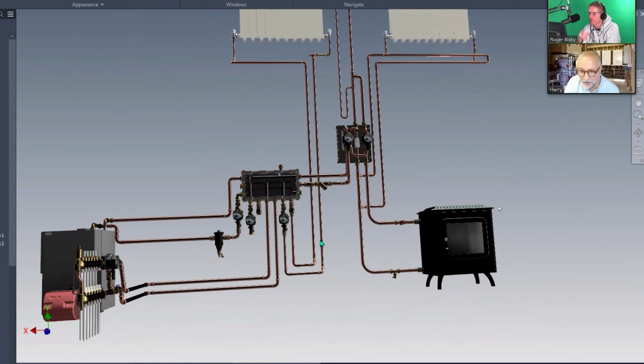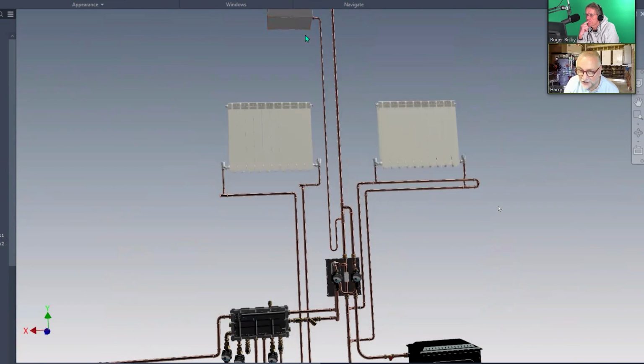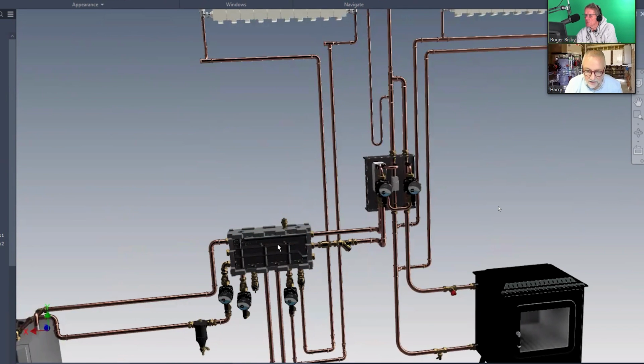So when we come out of that, what are we calling that unit, that box, by the way? This is the energy zone. So if you call that the energy zone, that's fed in from the feed and expansion tank. The open system has the expansion and cold feed, because you've got the plate heat exchanger in there. Okay, now I'm with it. That plate heat exchanger is your hydraulic separation between the solid fuel boiler and the heat pump. Correct. So this is a sealed system, this is an open system. Yeah, got it. Sorry, I was thinking it was all open vented, but it's not. Okay, that's fine.